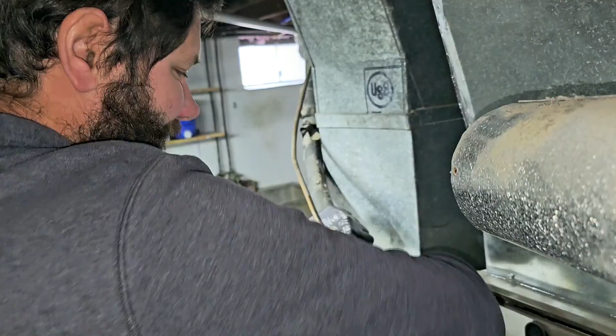We're going to get this coil cleaned. The customer actually asked me when I went up there and told them the problem, they said, 'Do we need a new unit?' I was like, 'No, you don't need a new unit. Your unit's brand new, you just need to have it cleaned, that's it.' Somebody who wanted to take advantage of the customer in that moment could have said, 'Yeah, you need a new unit.' Me, I don't believe that if anything's working, I don't believe in replacing it. I've said this in many of my videos, I'd much rather fix the equipment, repair it, than replace it, because you have more problems with new equipment than you do old equipment.